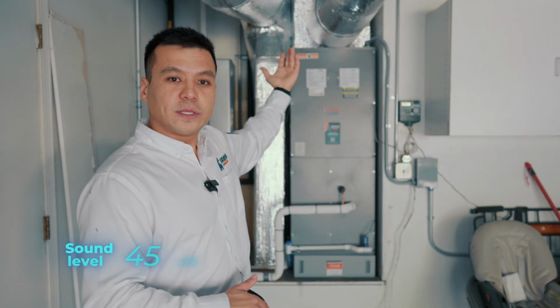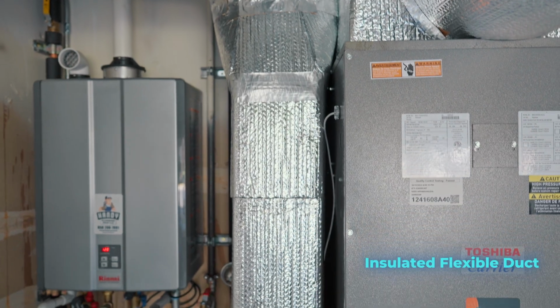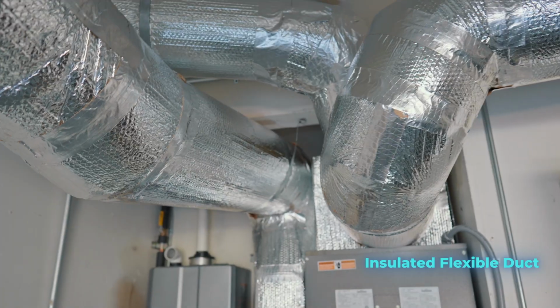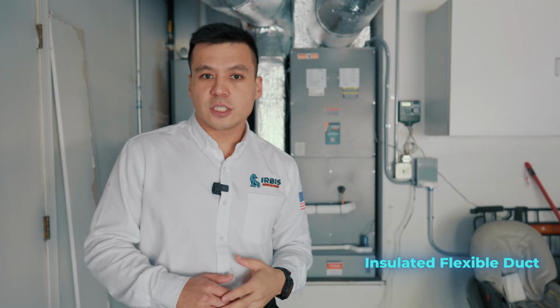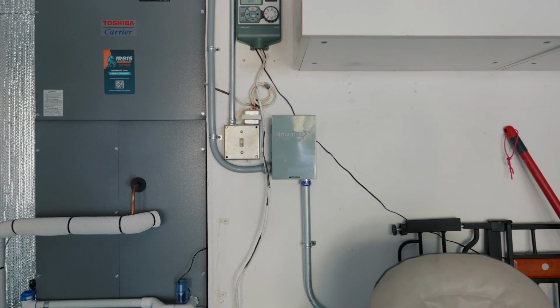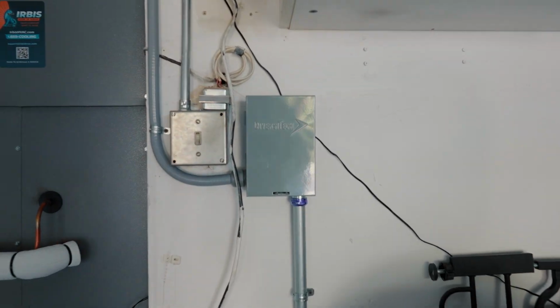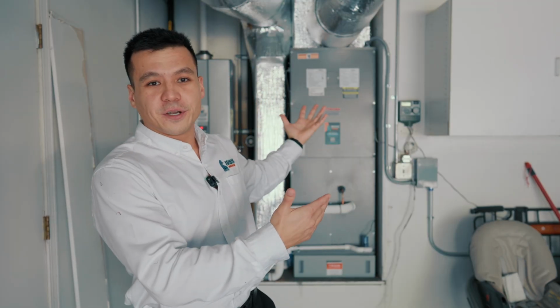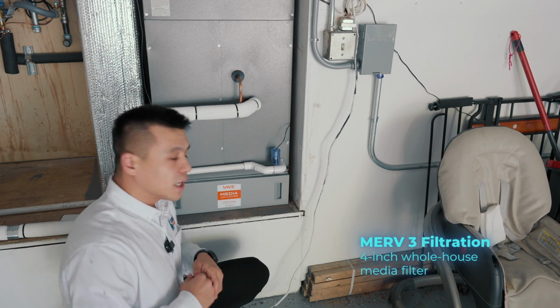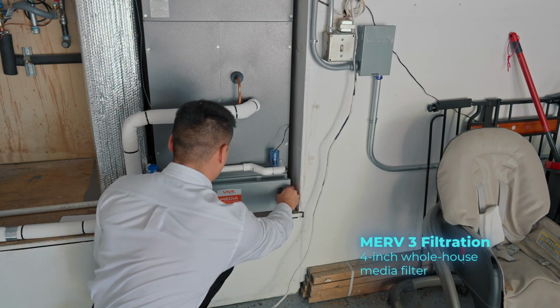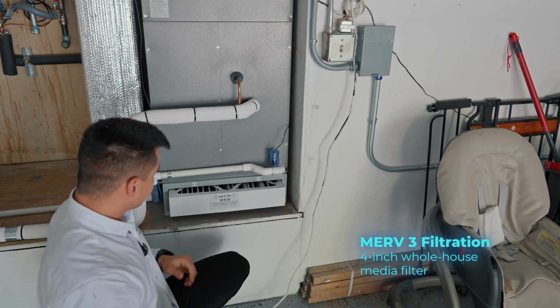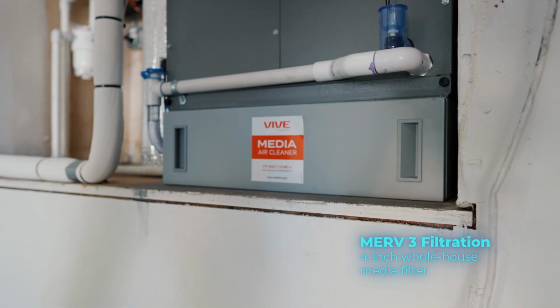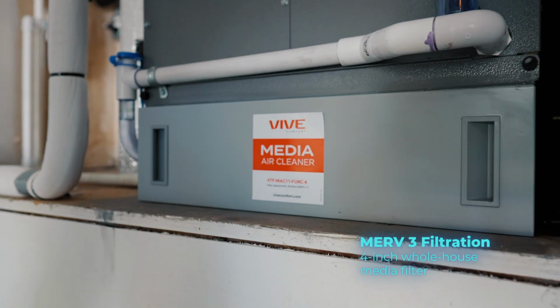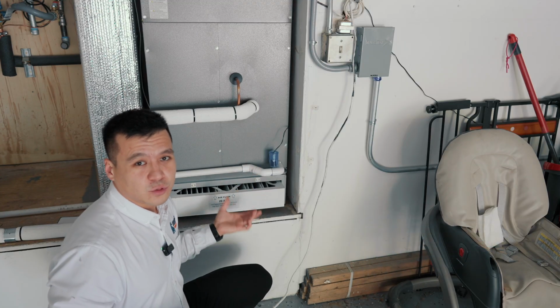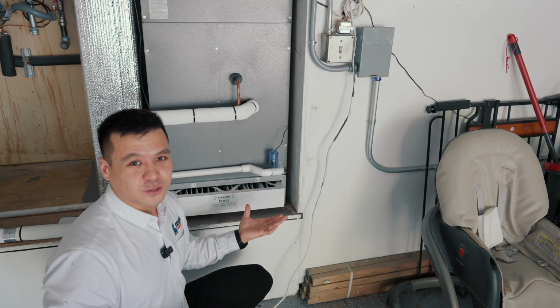As you can see, we insulated the plenum. All ductwork here is new, which is also insulated. This insulation helps to provide an extra layer to preserve the temperature inside the ducts, and of course it looks way better. So for the air filtration, we have a 4-inch media filter cabinet, which is easy to remove and to replace. We can replace it with a filter up to MERV 15, which will be hospital quality air filtration.